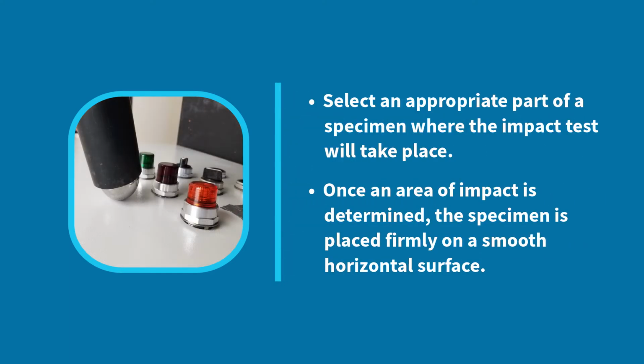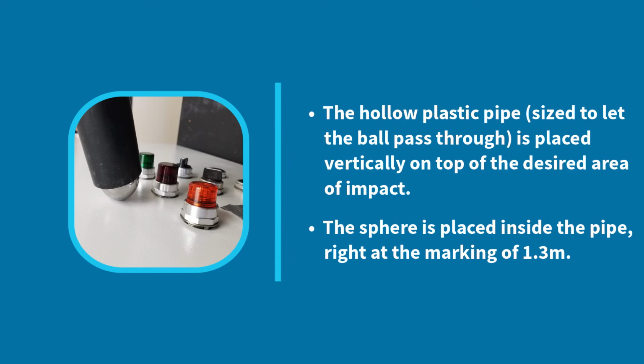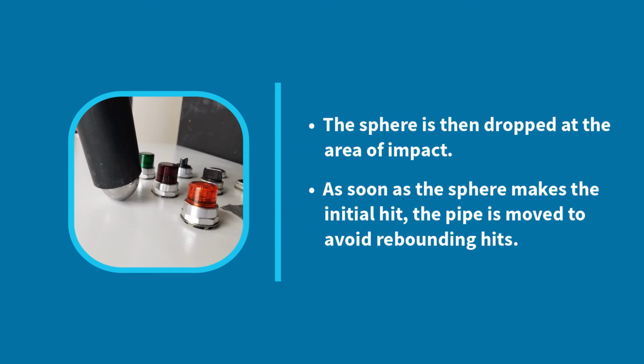Select an appropriate part of the specimen where the impact test will take place. Once an area of impact is determined, the specimen is placed firmly on a smooth, horizontal surface. The hollow plastic pipe, sized to let the ball pass through, is placed vertically on top of the desired area of impact. The sphere is placed inside the pipe, right at the marking of 1.3 meters. The sphere is then dropped at the area of impact. As soon as the sphere makes the initial hit, the pipe is moved to avoid rebounding hits.